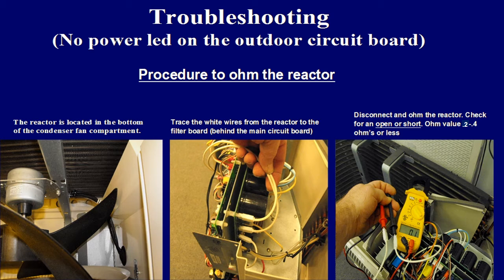Trace the 2 white wires back to the main board. Remove these wires from the board and check for continuity. A good reactor should show approximately 0.2 to 0.4 ohms. This value may vary some depending on the outdoor ambient temperature.